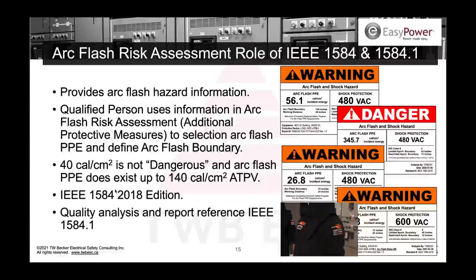The 40 cal myth again, I still see that in studies when I review them for clients. There is no 40 cal stop point for energized electrical work. It is not dangerous, and PPE actually exists up to 140 calories per centimeter squared arc thermal performance value. So I continue to bring up the 40 cal myth that we need to get that off the table, and it shouldn't be in a documented report by a P.Eng or a P.E. at all, right? And the risk assessment procedure that I mentioned earlier is the employer's responsibility, not the engineer doing this technical study and these technical calculations, all right?